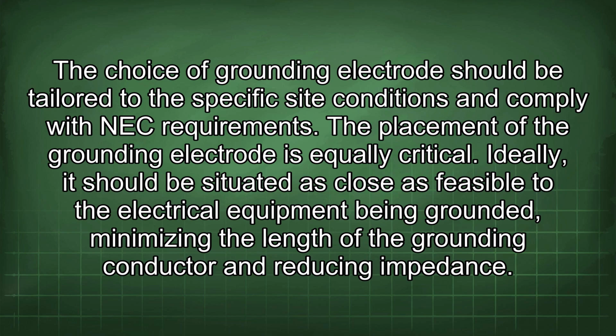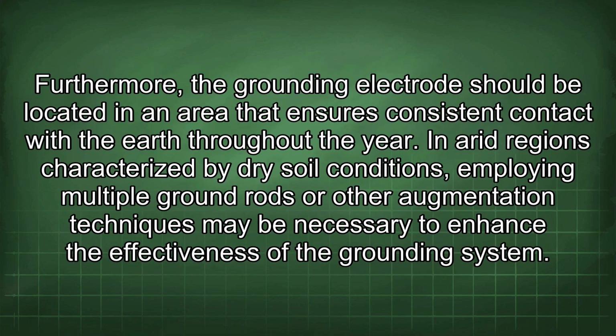The placement of the grounding electrode is equally critical. Ideally, it should be situated as close as feasible to the electrical equipment being grounded, minimizing the length of the grounding conductor and reducing impedance. Furthermore, the grounding electrode should be located in an area that ensures consistent contact with the earth throughout the year. In arid regions characterized by dry soil conditions, employing multiple ground rods or other augmentation techniques may be necessary to enhance the effectiveness of the grounding system.